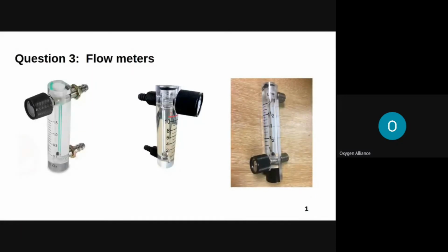All right. Thank you, Maui. So flow meters control the amount of oxygen released to the patient's outlet. And different flow meters come with different flow rates. Most of the concentrators we see around come with a maximum of 5 liters per minute, 8 liters per minute, or even 10 liters per minute. So to answer this question, the following are the factors you need to consider when you want to replace a flow meter picked from another oxygen concentrator.